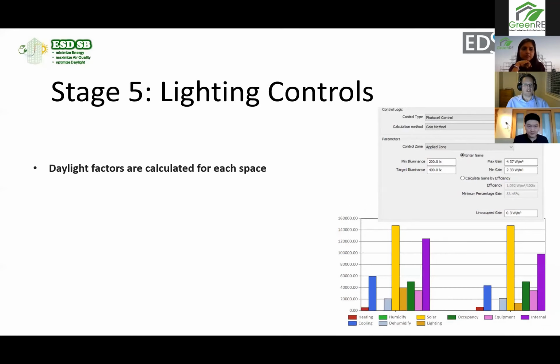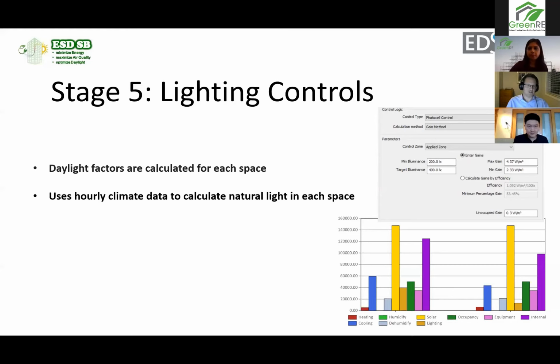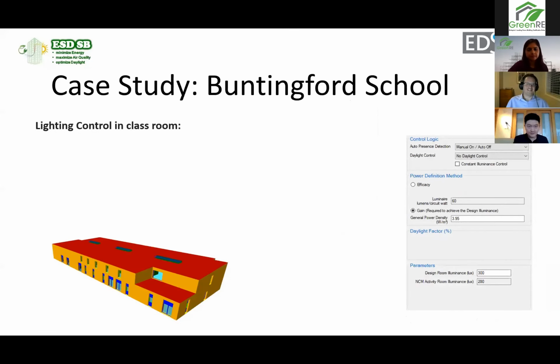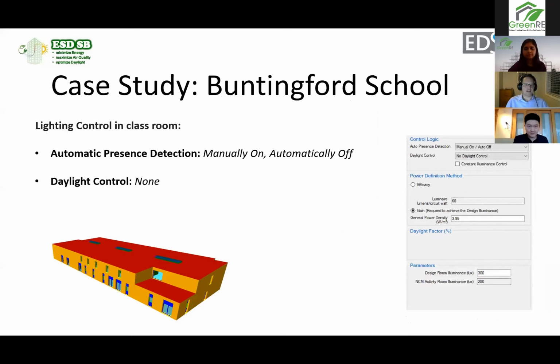For those lighting controls, we calculate the daylight factor for each of the spaces using hourly climate data. If we know the daylight factor and the amount of natural light outside, we know the amount of natural light inside each space on each hour. The user then enters the lighting efficiency and any control information, and that will produce the lighting gain. In our particular model, we had automatic presence detection, so the lights were turned on during the day and automatically switched off when people left the space. But there was initially no daylight control, and the general power density of the lighting was nearly 4 watts per meter squared.